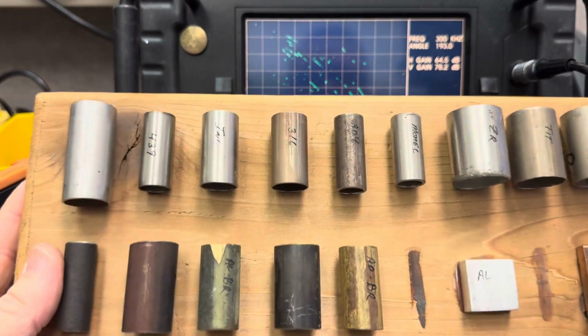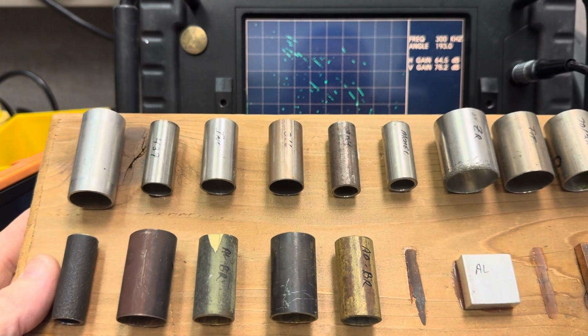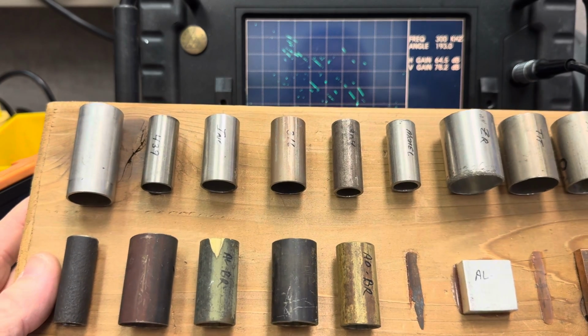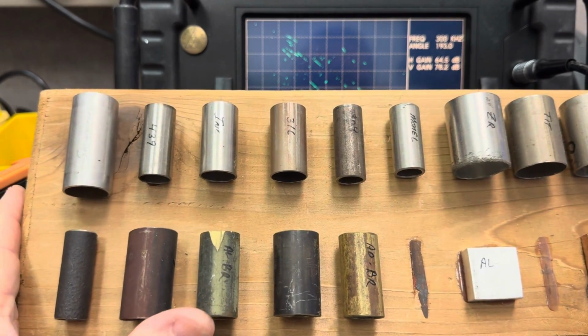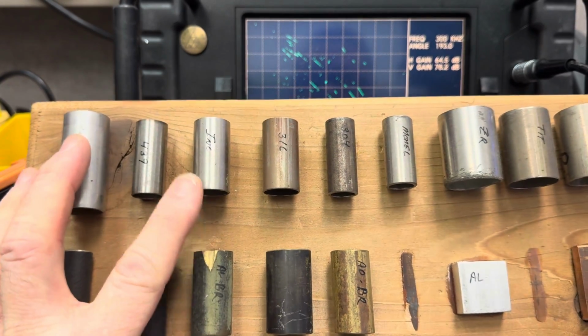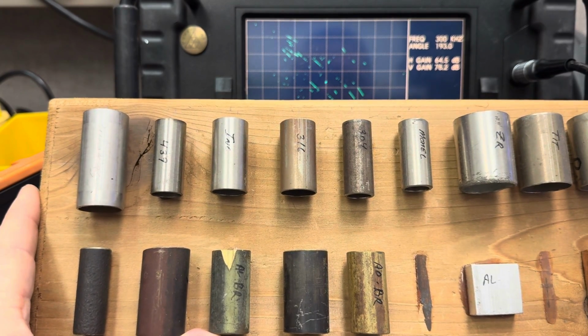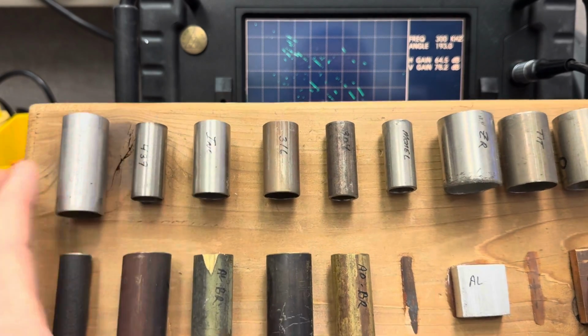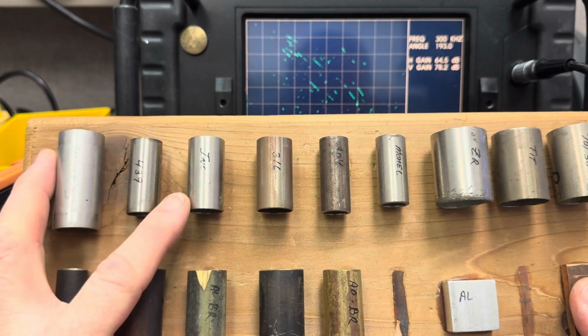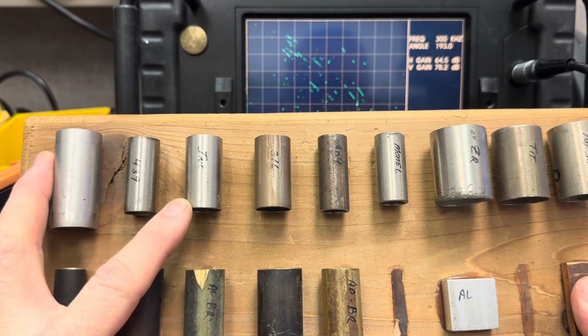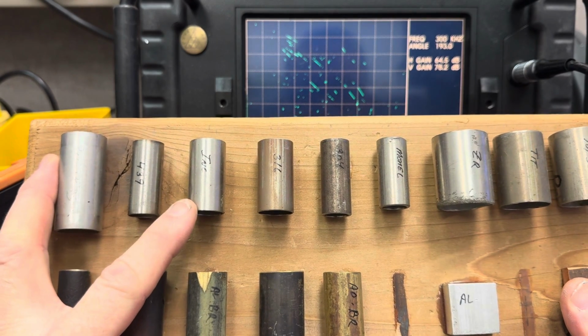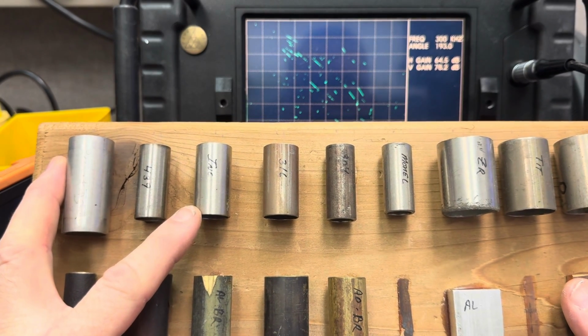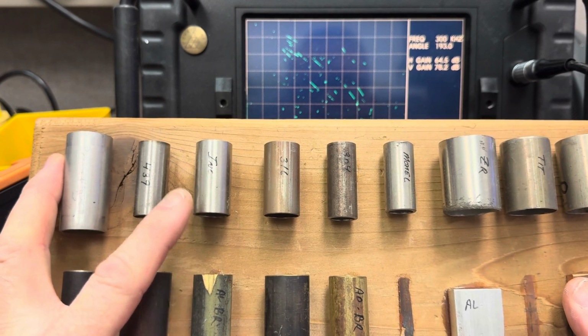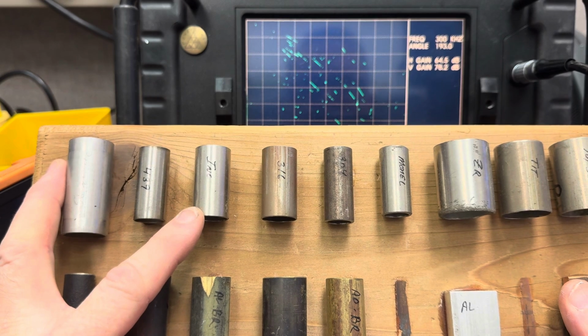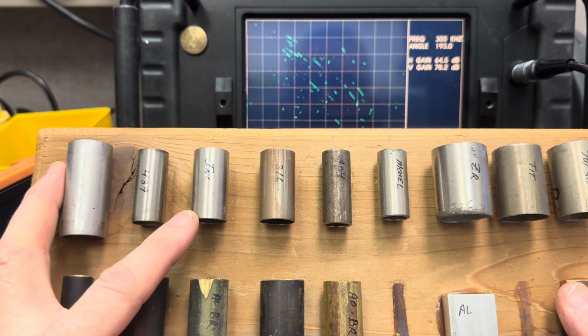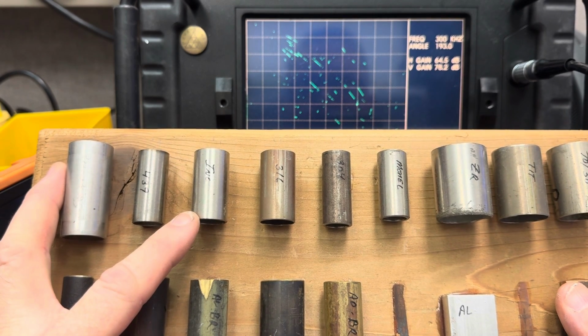And let's see, what else can we talk about these tubes? Depending on the type of tubing, you could have specific types of degradation that is most likely to occur. Yellow metals are famous for having ID pitting. Inconel 600 has been prone to a lot of cracking over the years. That's why they replaced a lot of the vessels that had 600 thermally treated tubing. They used to also plug 600 thermally treated tubes with I600 plugs, and typically all of those plugs have been removed and replaced with 690 thermally treated plugs. Because back in the old days, when you had thousands and thousands of 600 thermally treated plugs installed in I600 tubing, they would crack. So you'd have to go in there and inspect the plug rolls with a rotating probe.